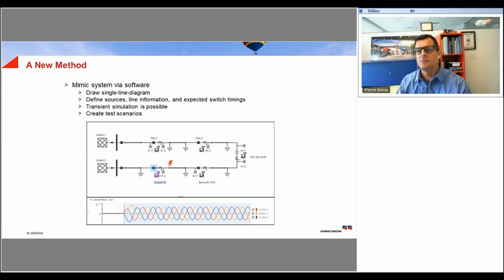Now, imagine this new method where a power system under test can be modeled in a single line diagram editor, and devices such as reclosers and circuit breakers can be placed within the network. In-feeds can be defined by entering various source information like the source impedance ratio. All the line data can be calculated by using line length and entering the line impedances. And loads in the network can be specified using active and reactive power data, which should be already available to you. Using all these data points, software can calculate the resulting load and fault values for any kind of user-defined test case. The behavior of each circuit breaker or recloser should be defined within this simulation software.